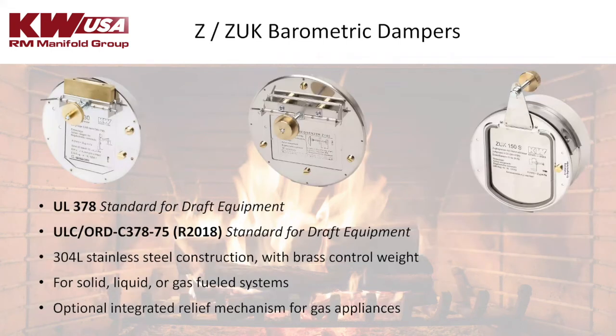So these are our ZUK barometric dampers, barometric draft regulators. They are listed to UL 378, standard for draft equipment. We have the same listing in Canada as well. They're made of 304L stainless steel, so you can use them in high heat situations, with a brass control weight. Just adjusting that control weight basically controls when that damper door opens and closes. So you can use them for solid, liquid, or gas fuel systems.